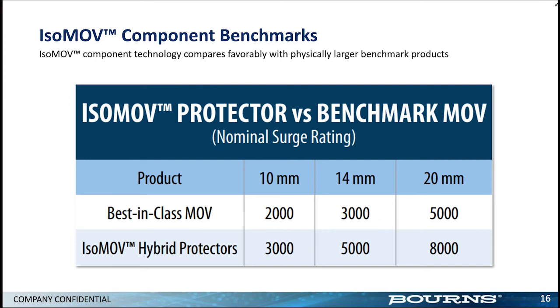Right. When you put MOVs in parallel, they don't add up directly, right? You're going to get some current hogging because these are not precision devices. We typically use a 40-60 split between two MOVs. And as you add more and more MOVs, you can do statistics and get some kind of bell curve. But yes, you do get increased current capability by putting more MOVs in parallel. You can do the same thing with IsoMOVs, because the clamping part of it is due to the MOV part. And the lifetime is improved because the IsoMOVs only age during transients, not all the time like a normal MOV would. I hope that answers the question.